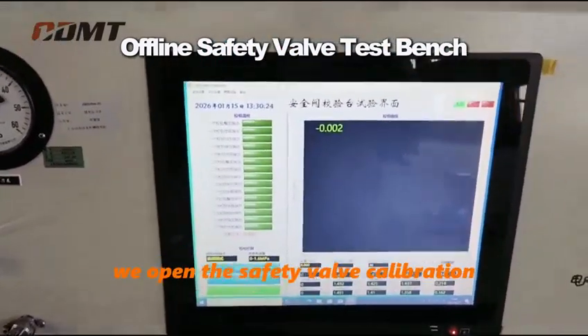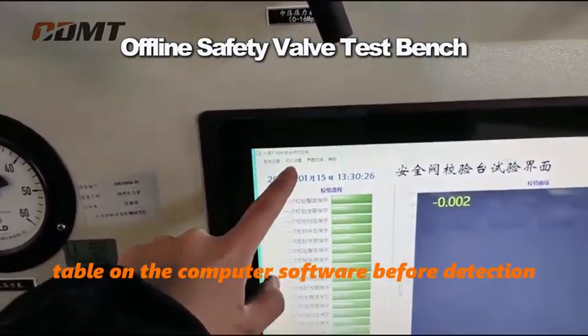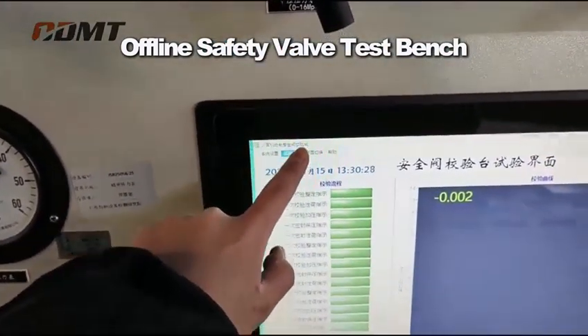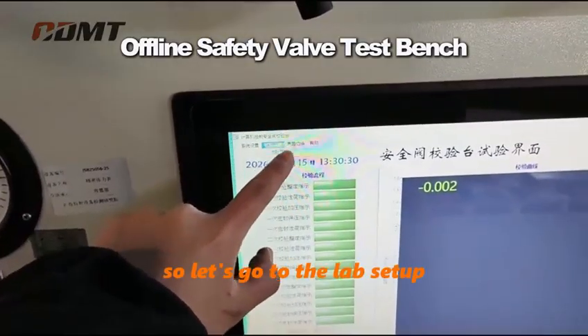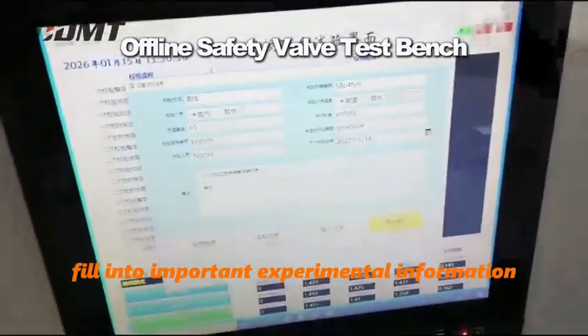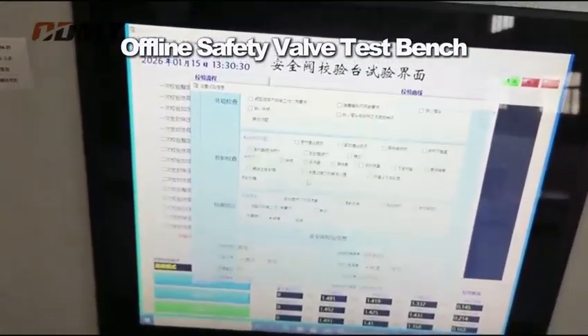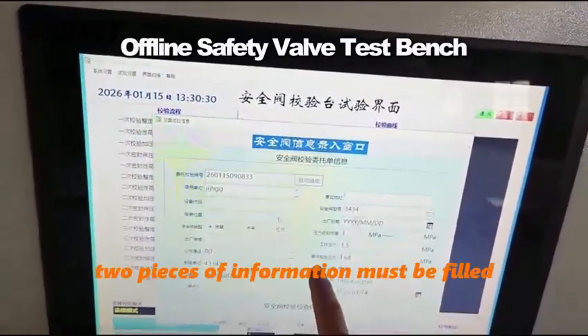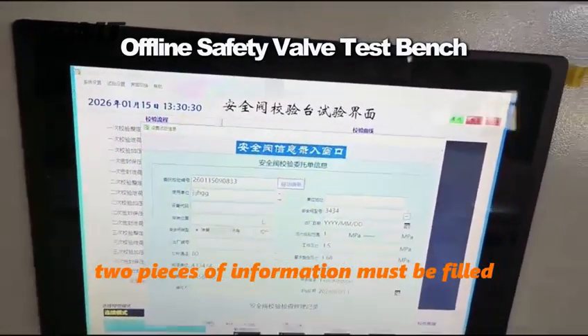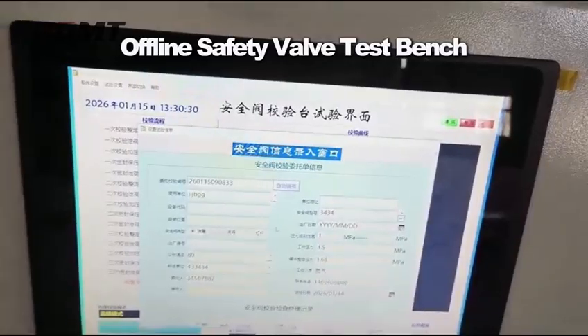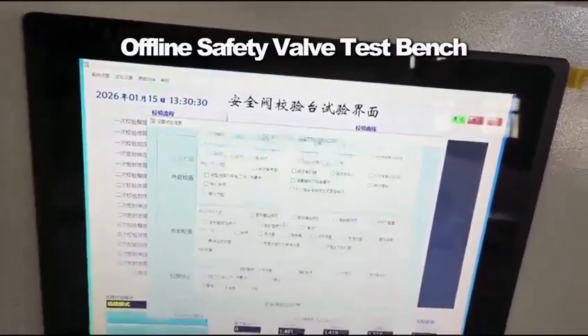And then, we open the safety valve calibration table software on the computer. Before detection, let's go to the lab setup. Fill in two important pieces of experimental information: the commissioned calibration number and the required setting pressure. These two pieces of information must be filled in. If you don't fill them in, it cannot be verified. After filling them out, click Confirm to enter.